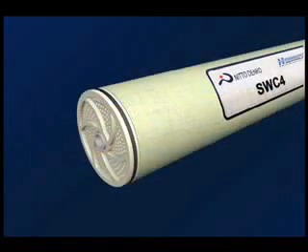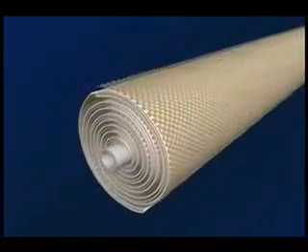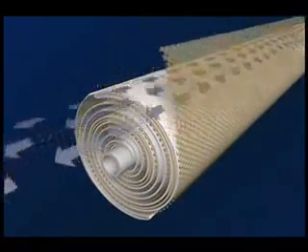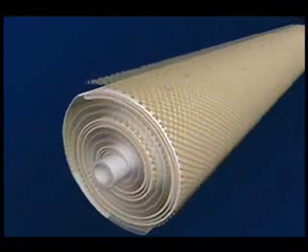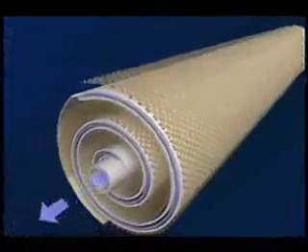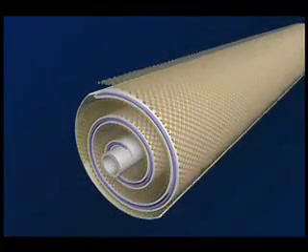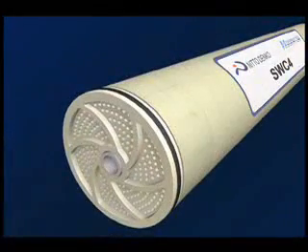With the back of the membrane completely sealed to the edges of the permeate spacer, the feed water is forced through the feed channel spacer contacting the front or barrier layer of the membrane. Clean water passes through the membrane surface into the permeate channel and then flows in a spiral direction to the center of the element and is collected into the core tube.